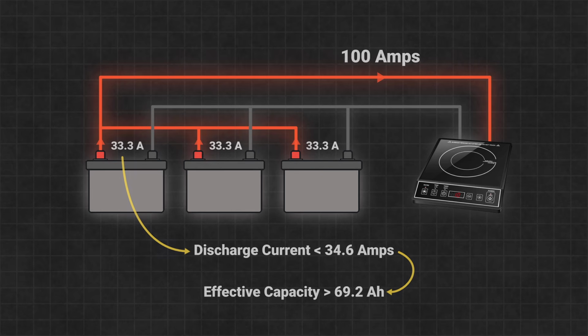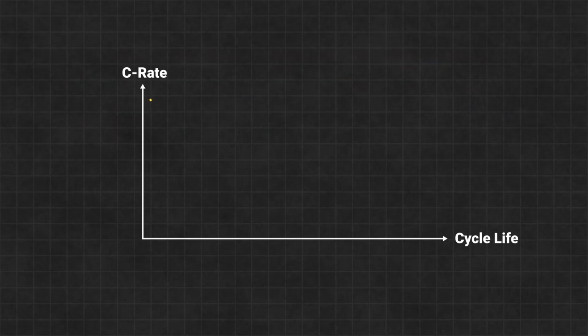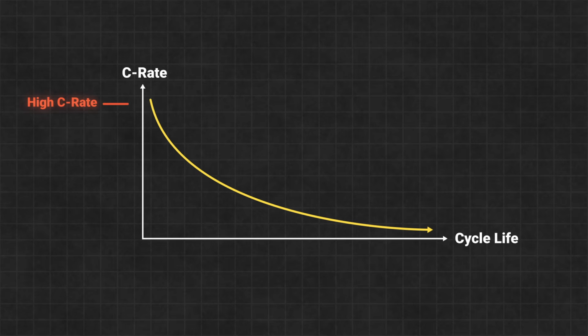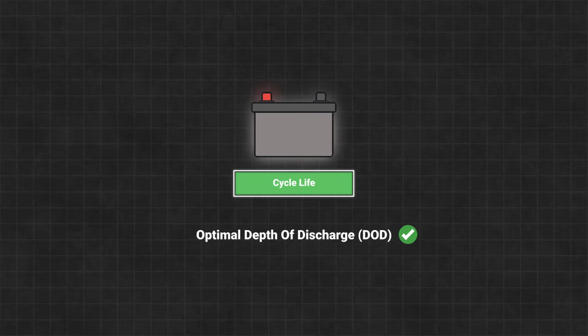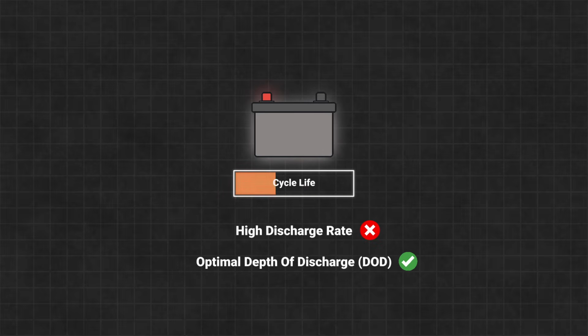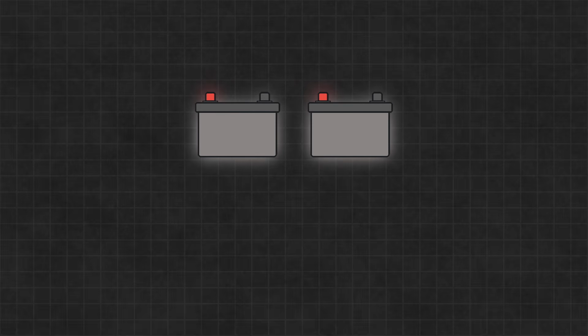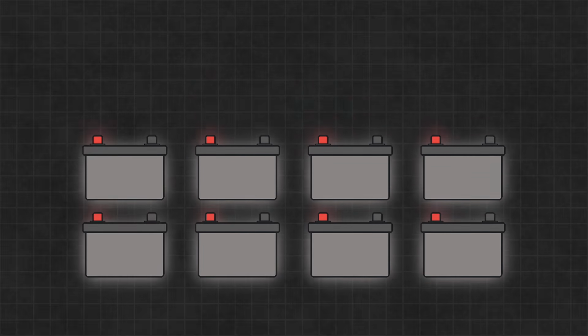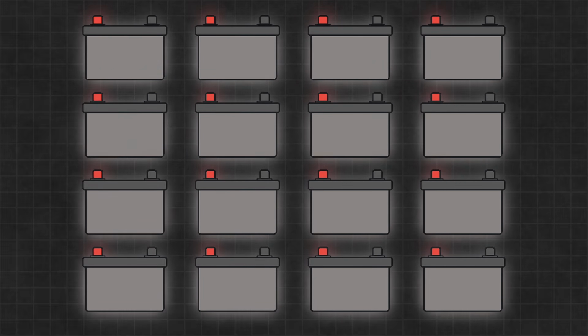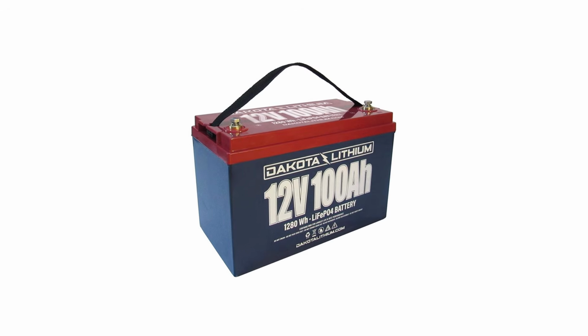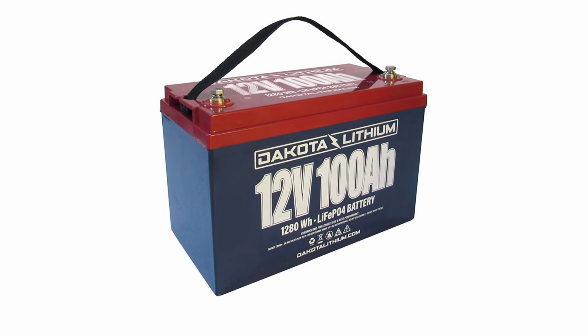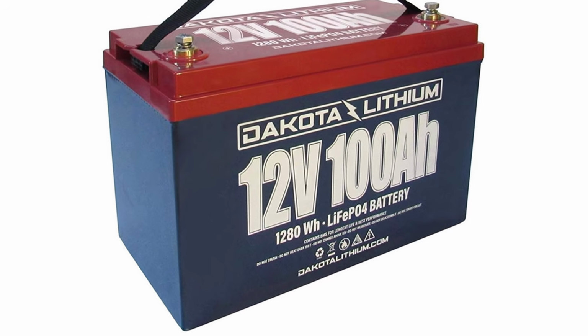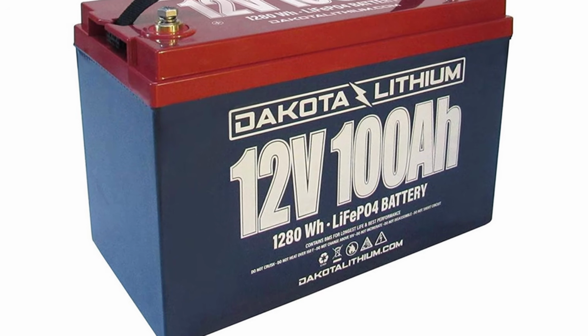Now, keep in mind that C-rate doesn't just affect capacity, it also affects the battery's lifespan. Higher discharge rates put more stress on the battery and accelerate degradation. So, optimizing for depth of discharge alone might not be enough, and you may still need to add more batteries just to reduce the discharge rate, which can quickly become very impractical. This is one of the main reasons why, in many cases, lithium batteries just make more sense, especially in setups where a high C rate is required.